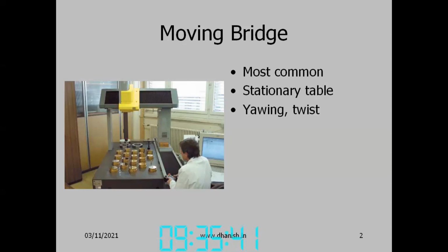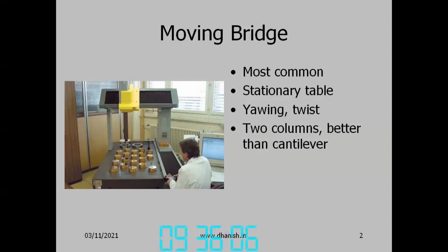So what is the problem with this design? When the bridge moves, ideally both the left and right side should move together. But sometimes if friction is more at one side, then there will be yawing or twisting. That is the major problem with this design. However, since there are two columns, the bridge is supported at both sides. That is better than the cantilever type CMM, where it is supported only on one side, and then the deformations are much more. Here we can see the moving bridge CMM being used to inspect CD molds.